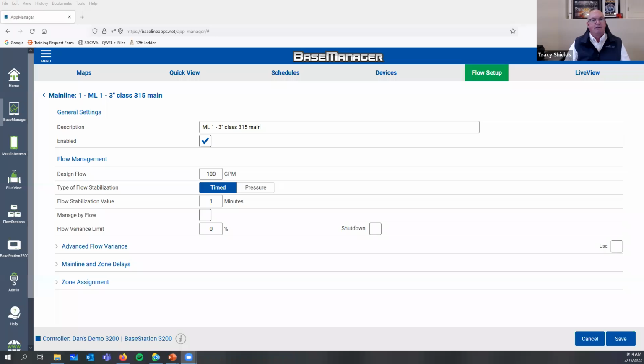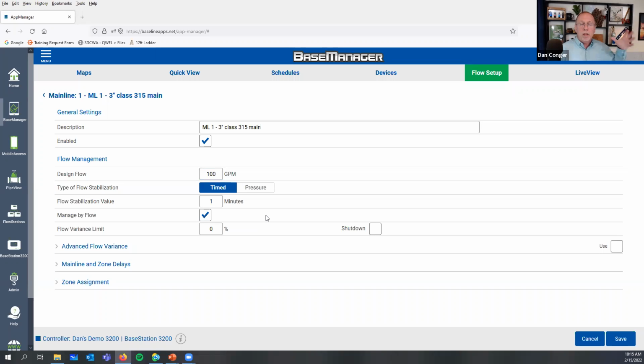So I have a friction loss chart here, and this is in the back of every major manufacturer catalog. Friction loss charts are really valuable tools, right? They tell you a lot of information. What do you recall what kind of info's in here, Tracy? You get flow and you get feet per second. You get velocity and friction loss across there. So right, pipe size, flow ranges for trying to stay under 5 feet per second. Right, industry standard is 5 feet per second. So I was able to look at a 3-inch class 315, which is different from 3-inch schedule and different from 3-inch polyethylene, right? All different flow characteristics. Looked it up and said, this can carry 100 GPM. That was a real number, and it's an important number to not guess at, because I'm going to use managed by flow. Managed by flow then allows me to maximize that 100 GPM.